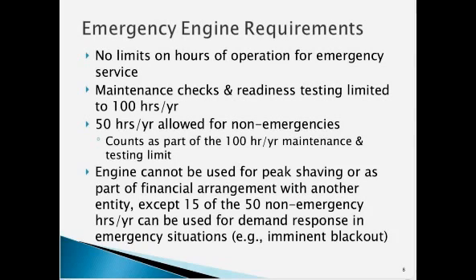What is an emergency engine? That's the next slide. We define it as used an unlimited amount of time for emergency service. So say an ice storm, that's a good example for today, hit and your power was out for a week, you could run it for all that time that your power was out, and there's no limit on that. Maintenance checks and readiness testing is limited to 100 hours per year.